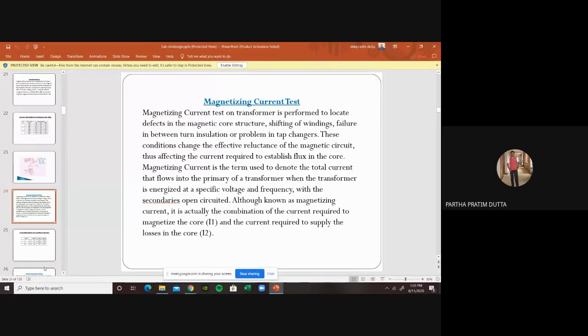The magnetizing current test usually we do for the transformer to see whether the magnetizing current for no load loss is properly working or not. That means the core is properly working or not. What we do is test the magnetic circuit to establish the flux in the core, or to activate the magnetic circuit. Current flows to the primary transformer with specific voltage and frequency, and the 11 kV LV side is kept open.